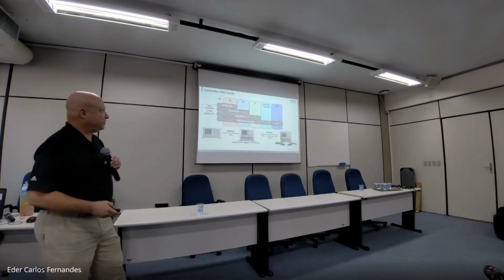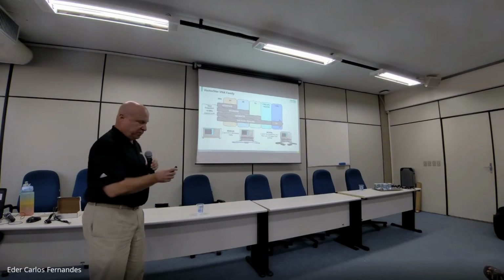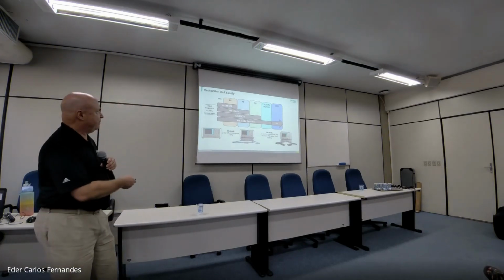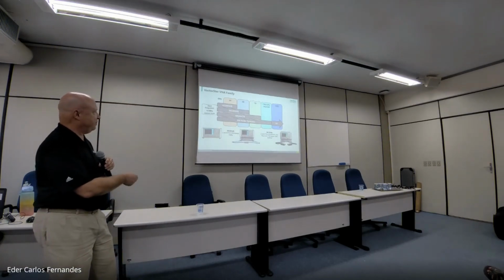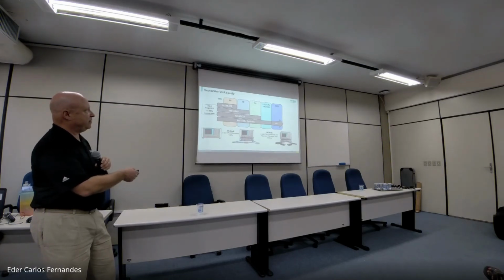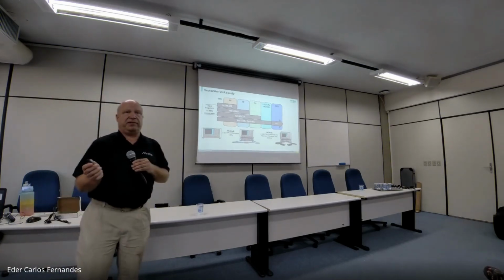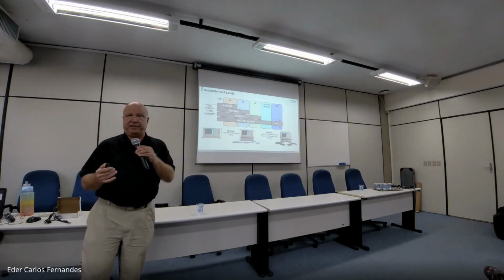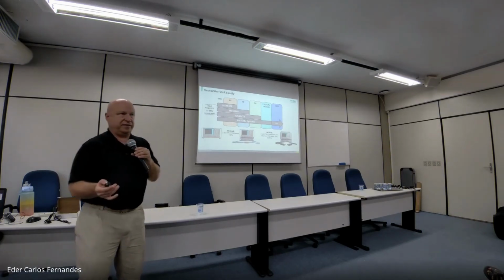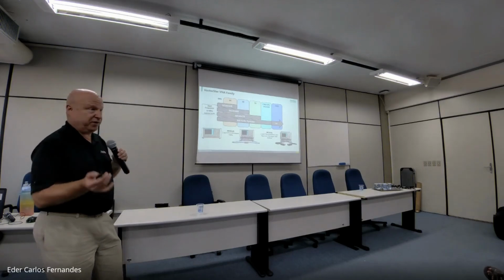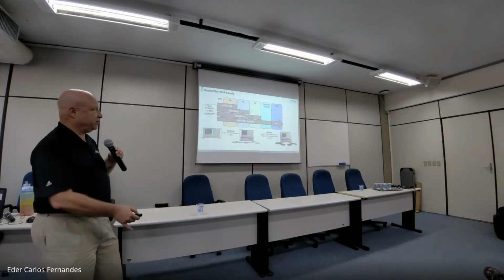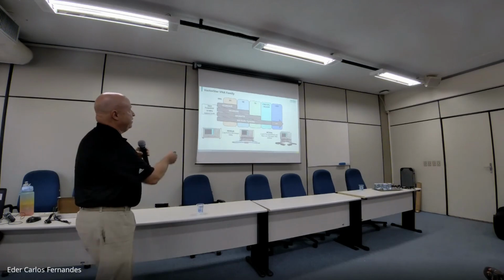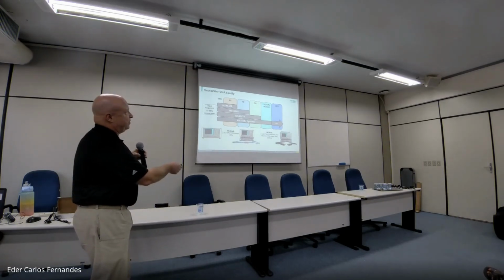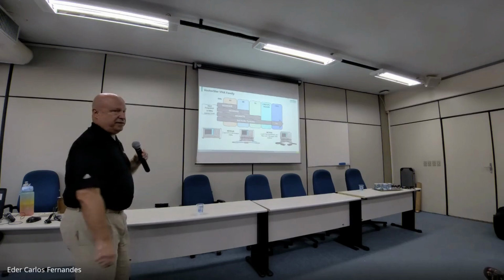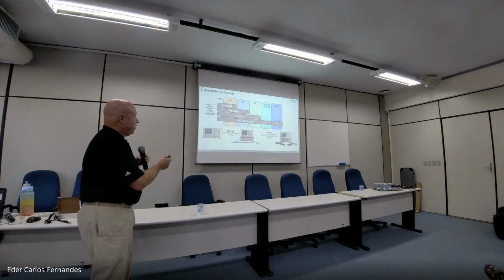All right, so on the VectorStar, we have basically 3 what we'll call baseband models or mainframe VNAs, 2-port VNAs, 20 gigahertz, 40, and 70. The most popular one is the 70 because it's really the basis for higher frequency systems, because you don't want any gaps. So if you're going to do a broadband system like the 220 gigahertz broadband system here at Unicamp, you need to start with the 70 gigahertz to be able to upgrade to these higher ranges. So that's our top selling VNA, the 70 gigahertz 2-port.